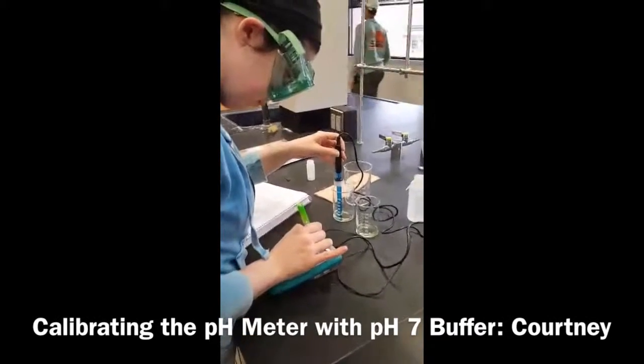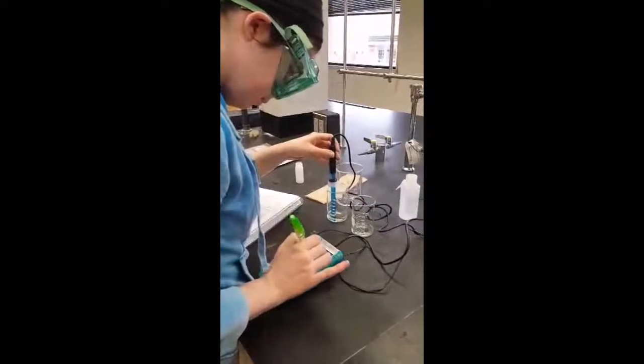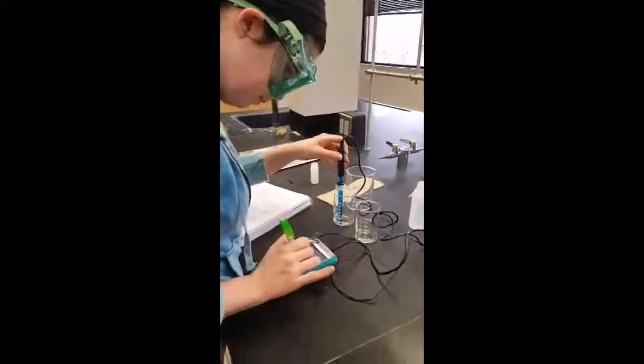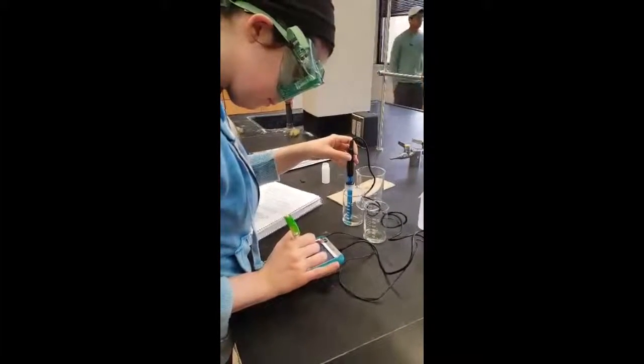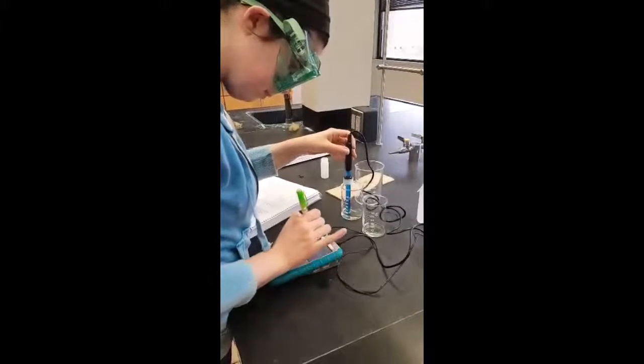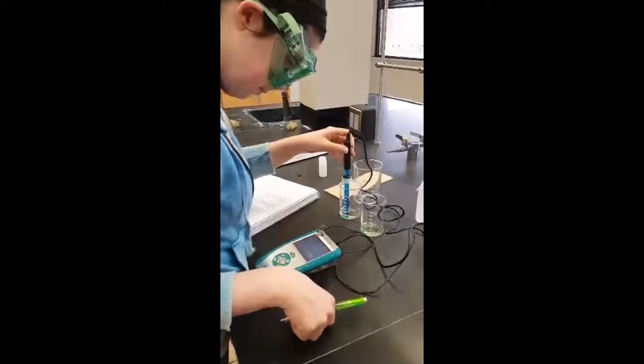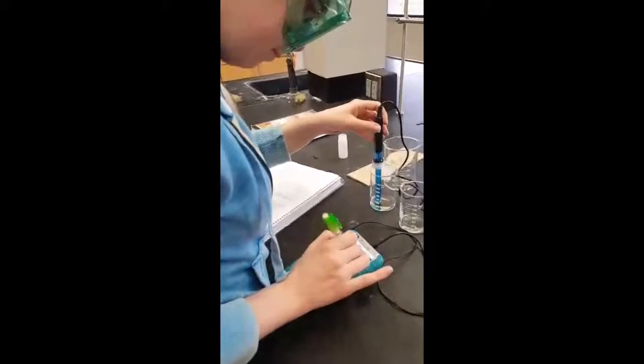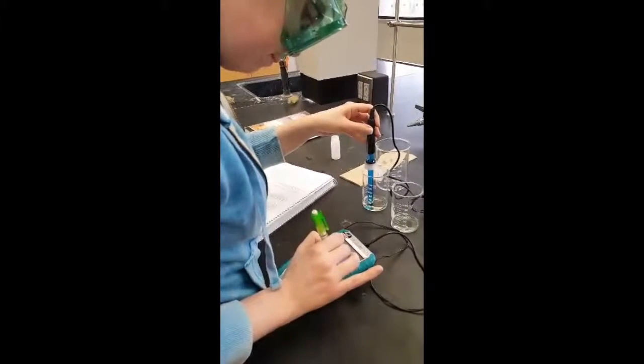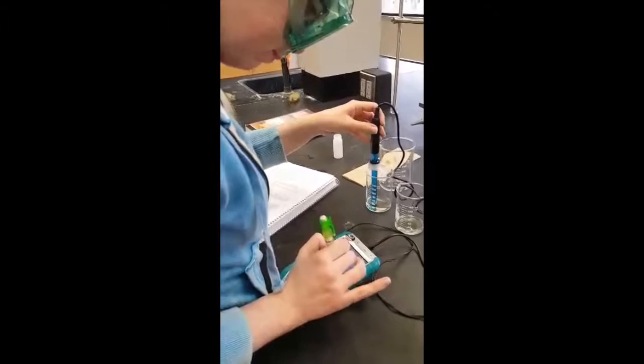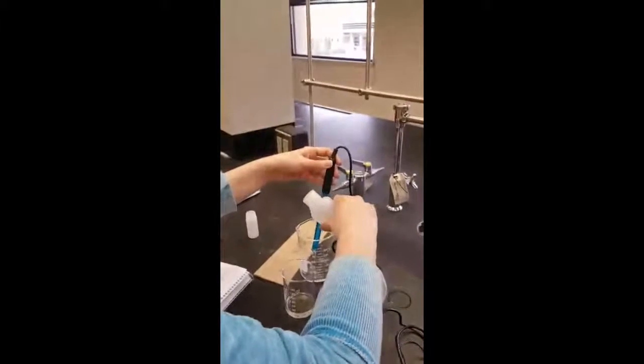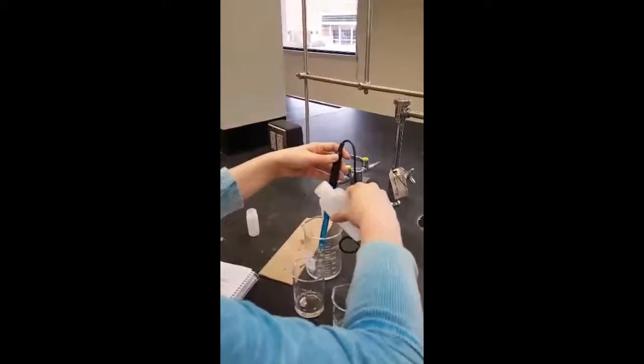To calibrate the pH meter, I first had to have two buffer solutions, one with a pH of 7 and one with a pH of 4. Then I took the probe out of the solution after I set up my pH meter. I rinsed it with distilled water over a waste beaker, then patted it dry with a paper towel, then placed it into a beaker with the buffer solution pH of 7, which is green.